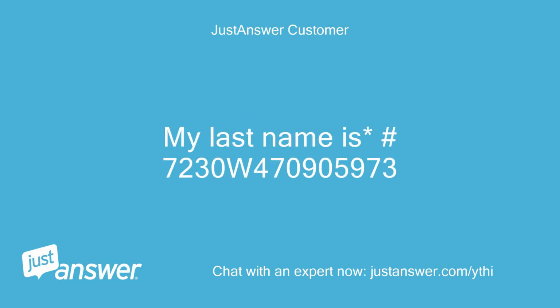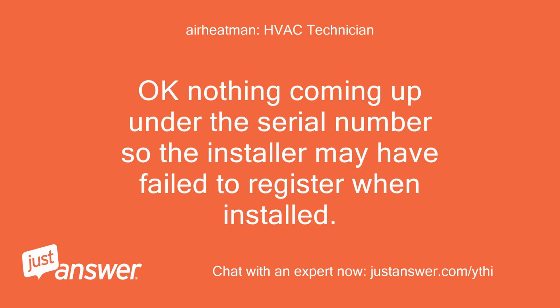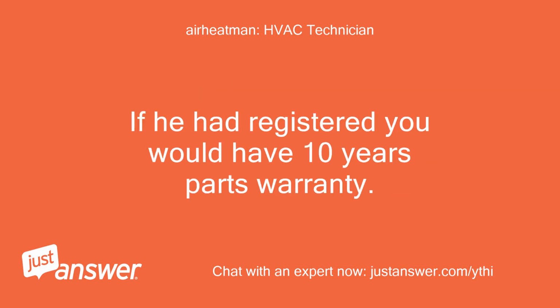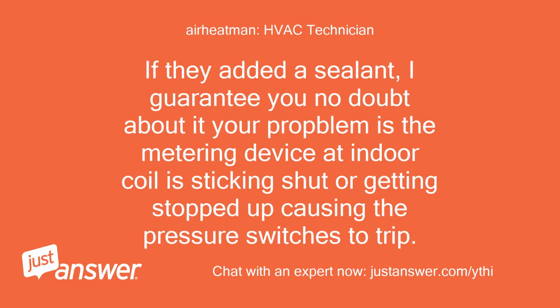Okay, nothing coming up under the serial number, so the installer may have failed to register when installed. If he had registered, you would have 10 years parts warranty. If they added a sealant, I guarantee you, no doubt about it, your problem is the metering device at indoor coil is sticking shut or getting stopped up, causing the pressure switches to trip.